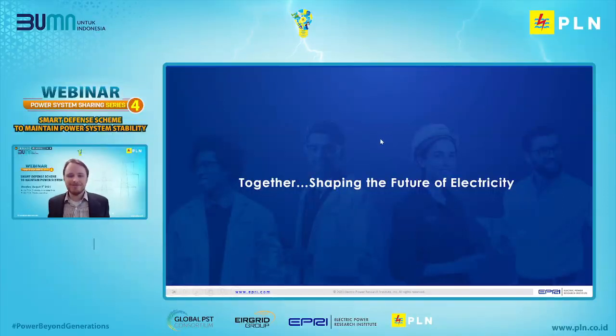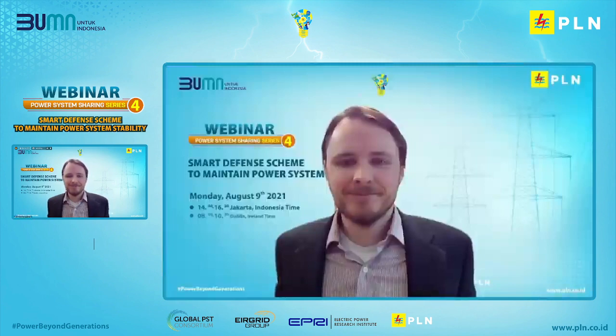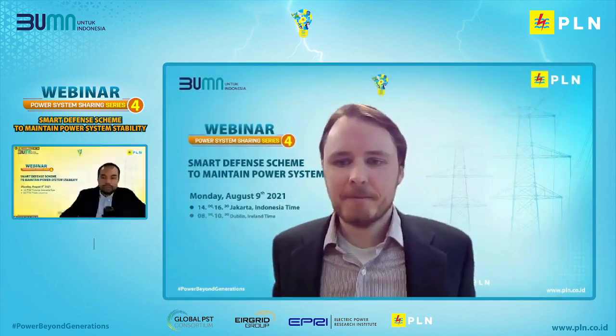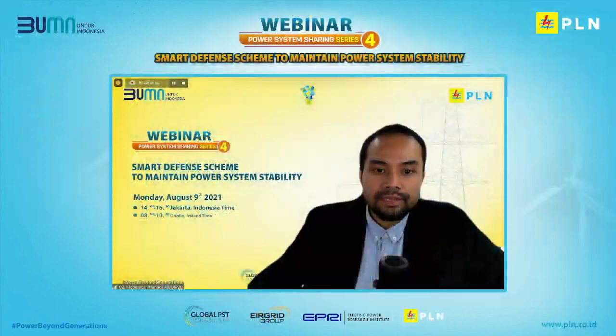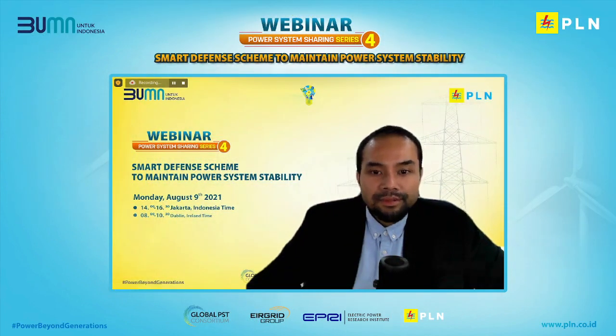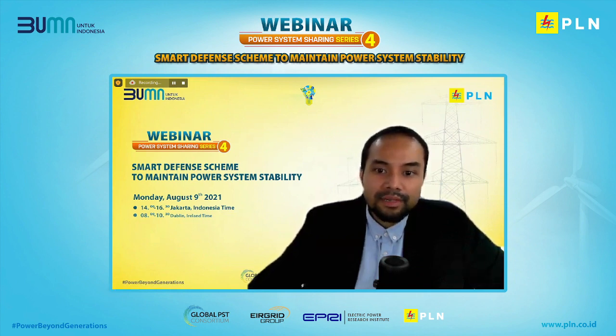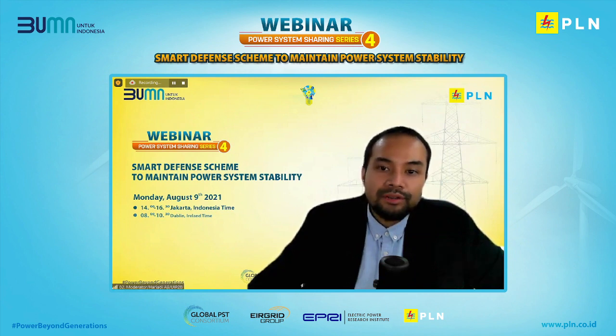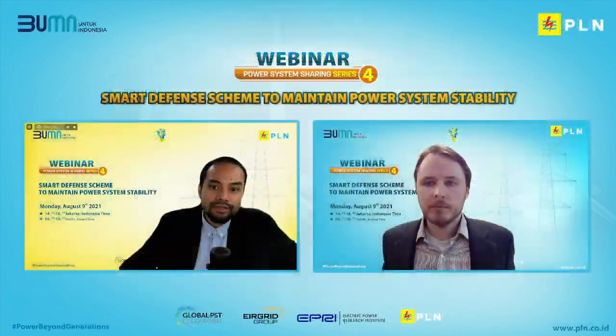Thank you very much. Thank you very much, Mr. Sean McGuinness, for such an excellent presentation about System Integrity Protection Schemes. I can conclude some important points from your presentation. SIPS is an automatic grid protection system used to detect abnormal conditions and designed to take corrective action other than tripping the faulted component. You also delivered some practical, conventional, and modern examples about the philosophy, with the complete reference below the scheme. I believe it will be a very good reference for us.